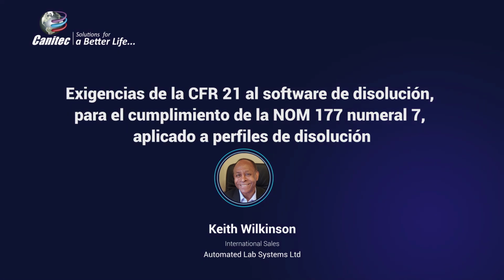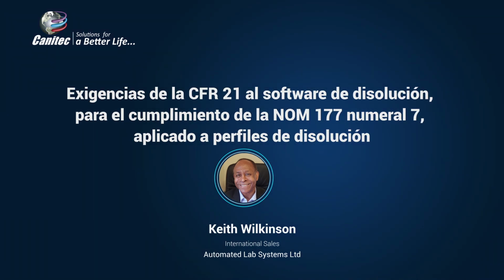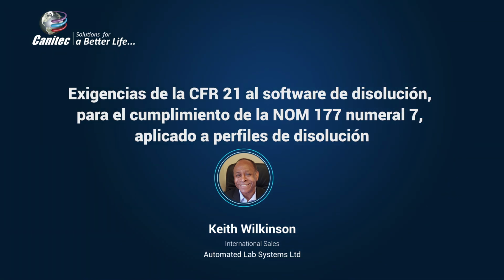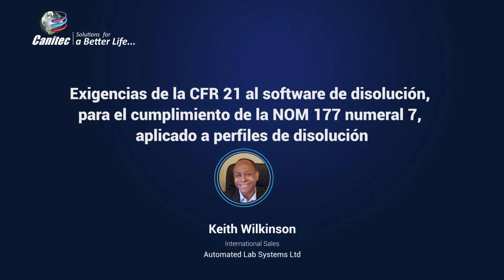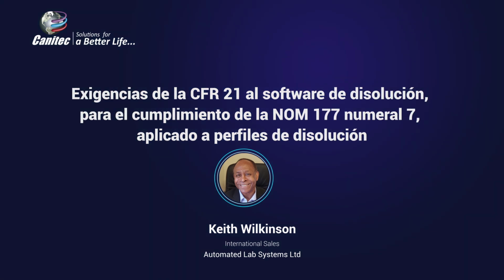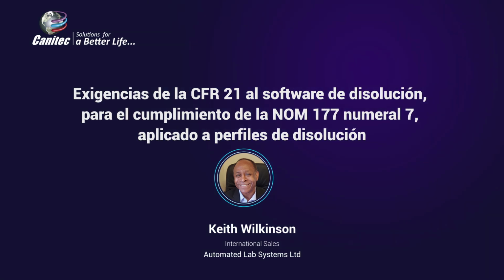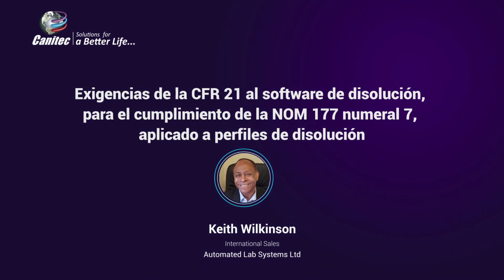So I press continue, and the software will now check the temperature of the dissolution tester, irrespective of which one it is. So the operation with this software is independent of the dissolution tester or the spectrophotometer. Once the software has reached the criteria which I set, it will pump a blank solution baseline and then ask me to continue.